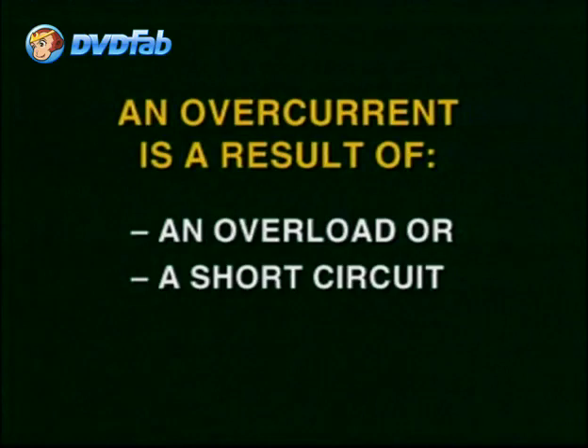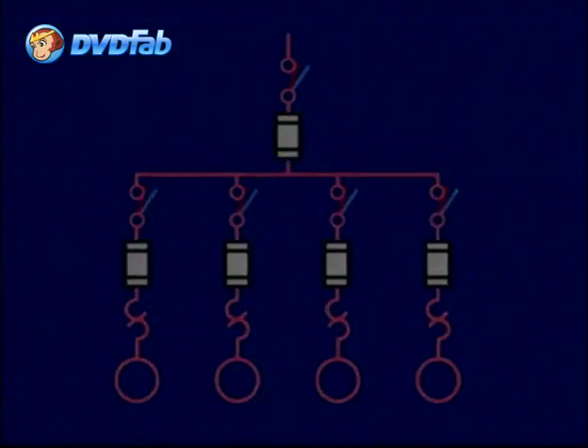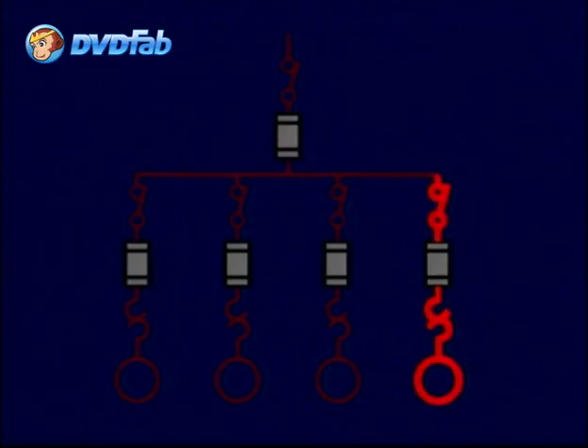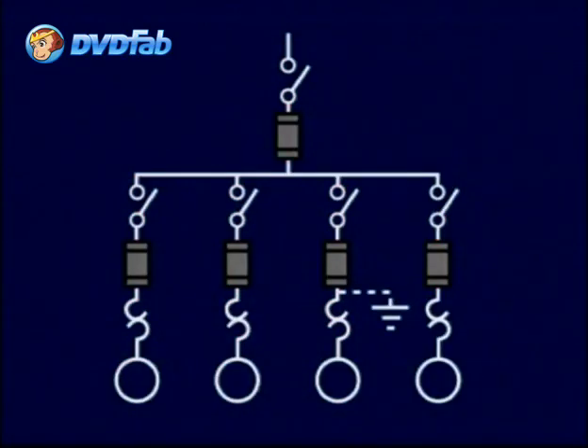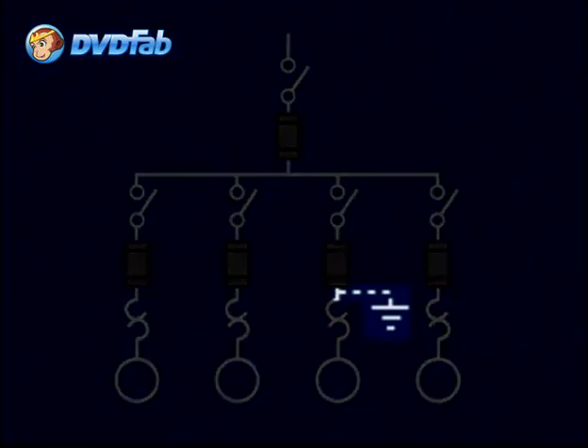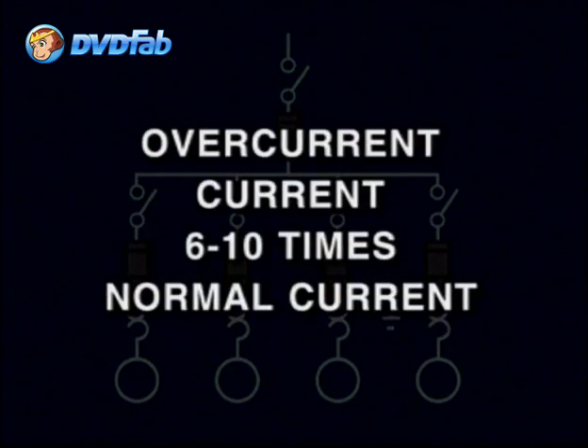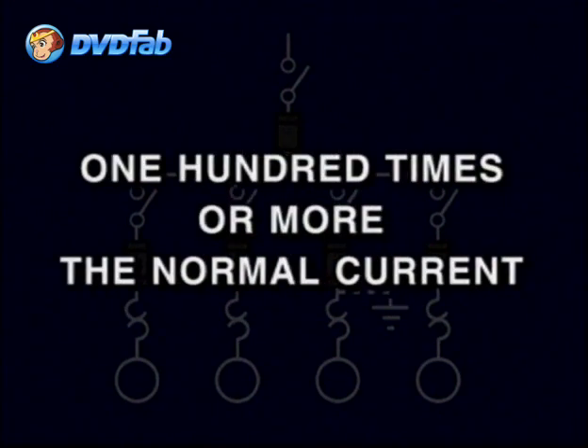Let's first define what an overcurrent is. An overcurrent is a result of an overload current or a short circuit or ground fault current. The overload current is an excessive current relative to the normal operating current, which is confined to the normal conductive path provided by conductors, other components and loads, such as motors, that will form part of the power distribution system. We'll cover overload protection of motor loads in a little while. A short circuit or a ground fault current is an excessive current which flows outside the normal conducting path. While overloads are most often at no more than 6 or 10 times the normal current levels, short-circuit currents can be hundreds of times that of the normal operating current.